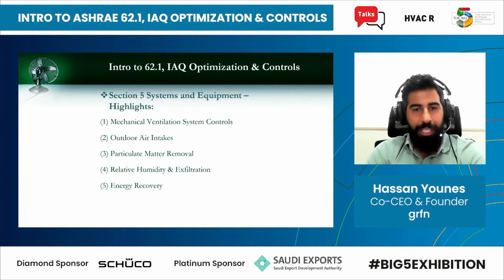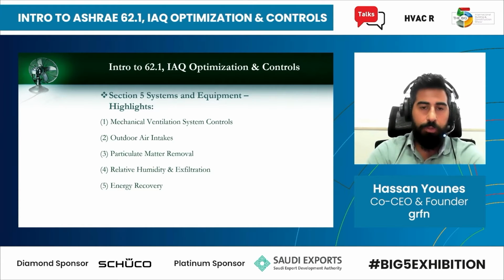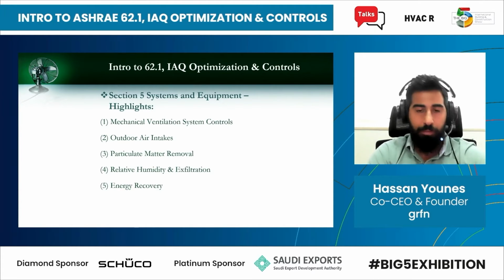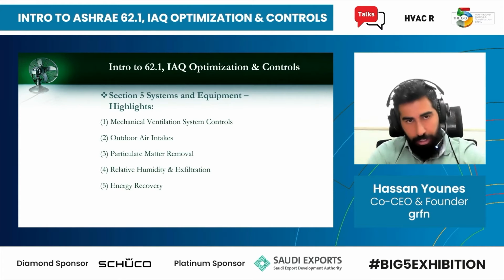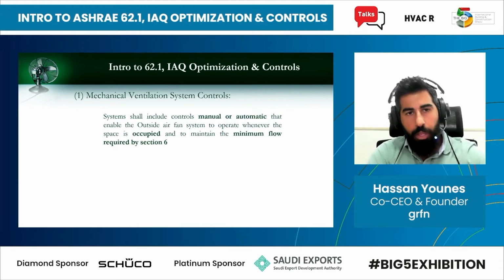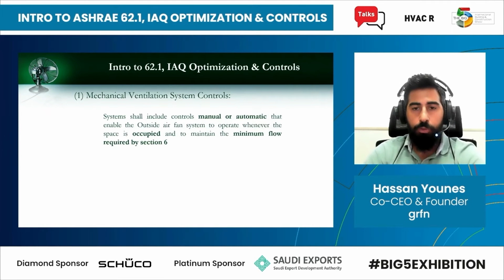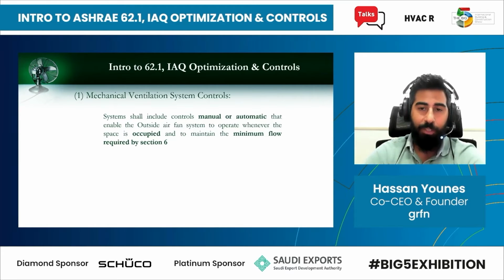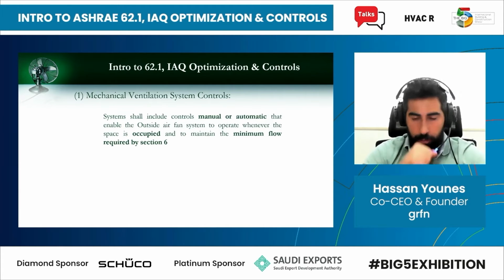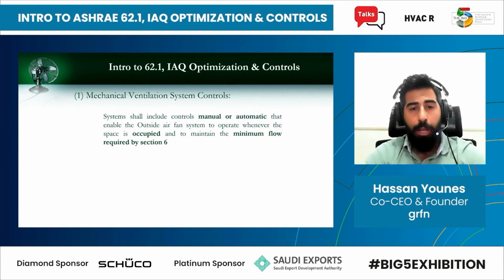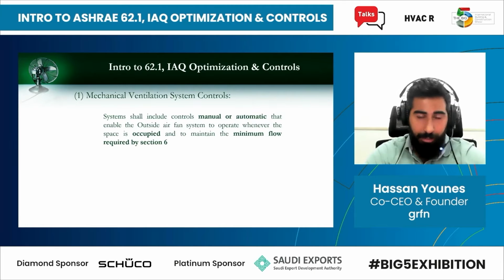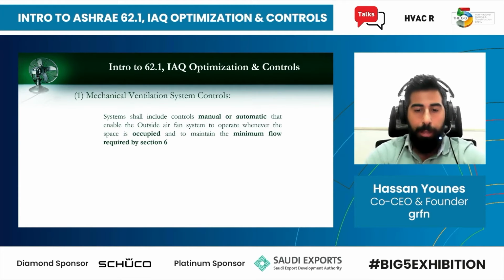Section 5, systems and equipment highlights. It talks about mechanical ventilation system controls, the outdoor air intakes, particulate matter removal, relative humidity and exfiltration, and also a bit on energy recovery. In terms of controls, it says that systems shall include controls, manual or automatic, that enable the outside air fan system to operate whenever the space is occupied and to maintain the minimum flow required by Section 6. So it basically tells you that whenever there are people inside the building, the ventilation system should be turned on. If there are no people in the building, then there's no issue.